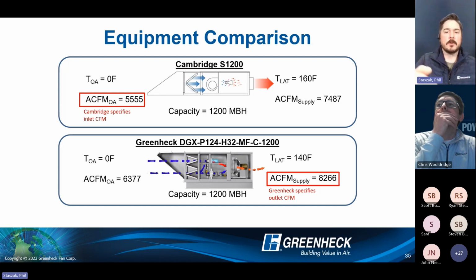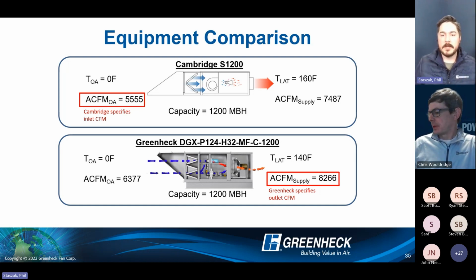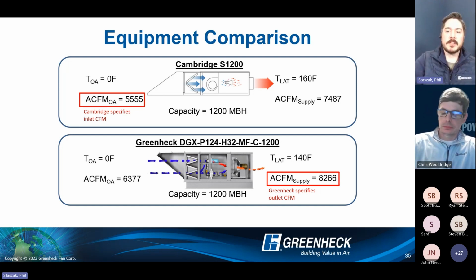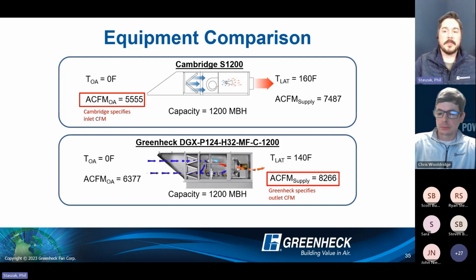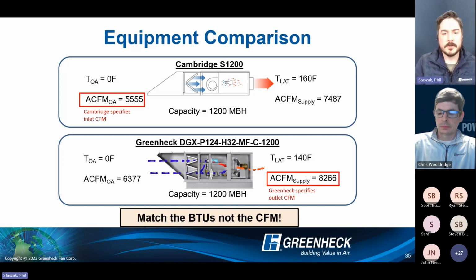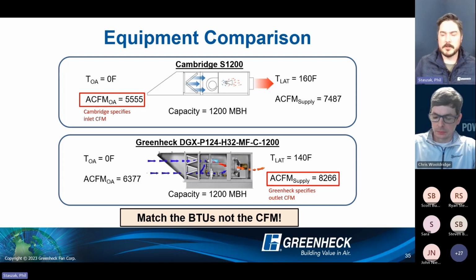Truly, once that airflow is being heated up, we're both providing 1,200 BTUs or 1,200 MBH into that building, but effectively at 160 degrees or 140 degrees. And truly, they're delivering that airflow at 7,487 versus our 8,266. So yes, it's slightly higher airflow, but don't get too tripped up on what that looks like on paper, because remember that it's inlet CFM that the Cambridge unit looks at. So there's a lot of confusion around that. BTUs are BTUs. Again, it's just being introduced at 160 versus 140. People can argue there are definitely more BTUs available at that elevated discharge air temperature. I can't argue with that.